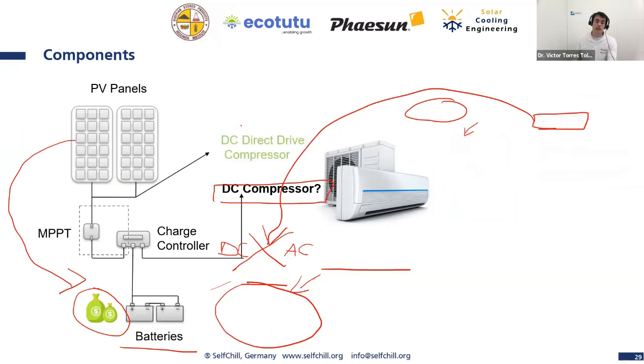What else? You can even use a DC direct drive compressor. What does it mean? It means you can run your compressor, your cooling unit, your heat pump, even without the use of batteries. So in this case, we don't have batteries, we don't even need a charge controller and so on, and we could run the cooling units directly from PV panels. Our cooling units can do both. They can run with batteries, or they can also run totally without batteries, which might be an advantage in some cases.